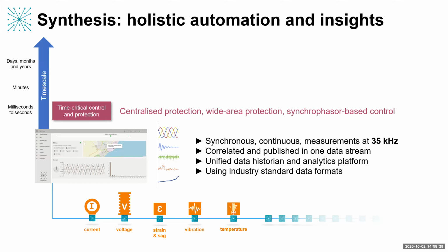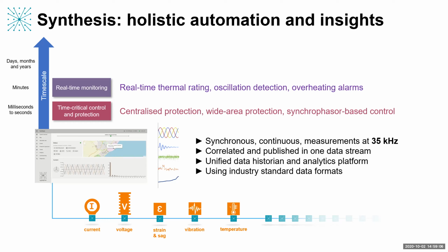The first timescale is the really time-critical, sub-cycle protection functions, which we've demonstrated in the past. On more human timescales, we can provide the information needed for real-time thermal rating of cables. We can also do things like oscillation detection quite readily because we see the full waveform and every single frequency that's going on.